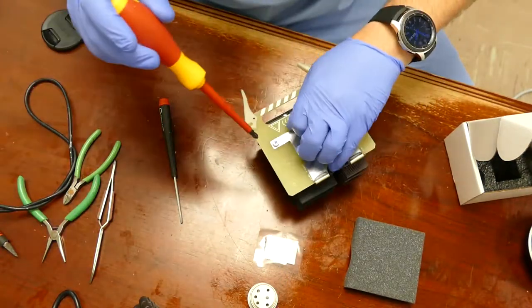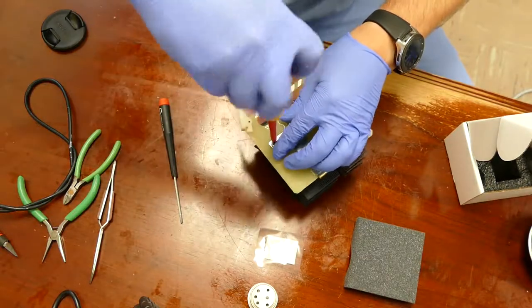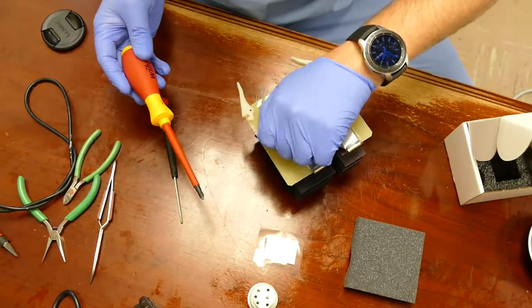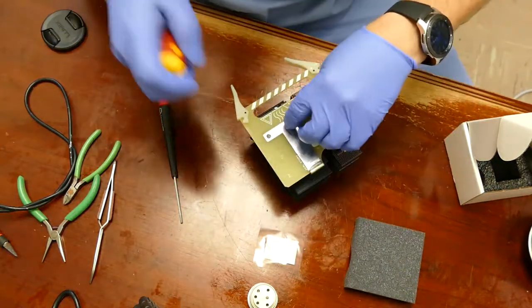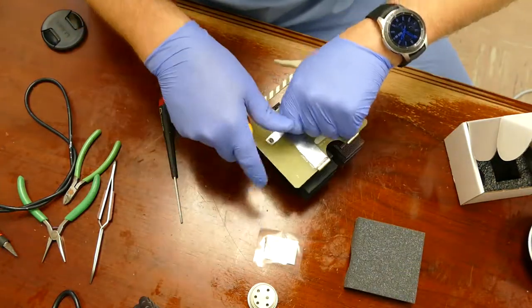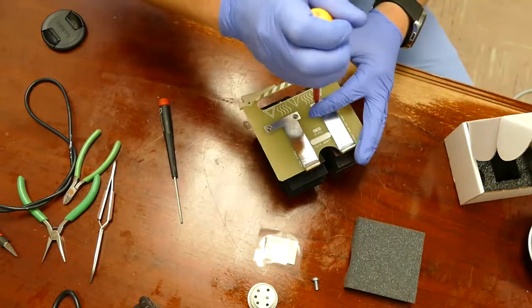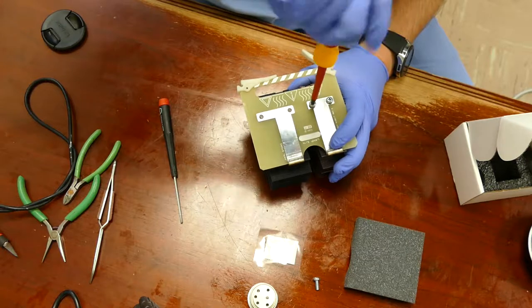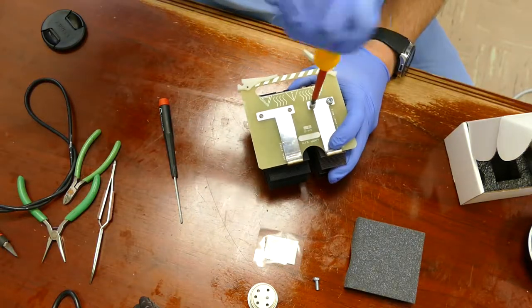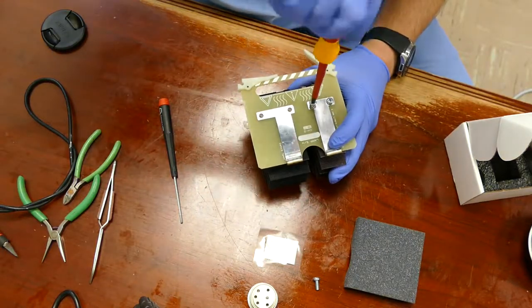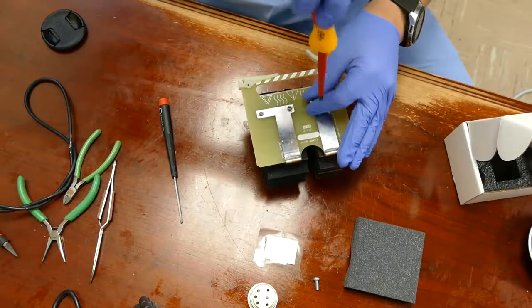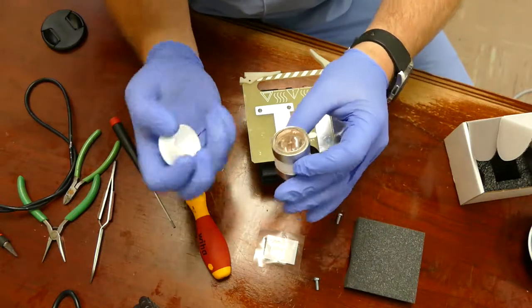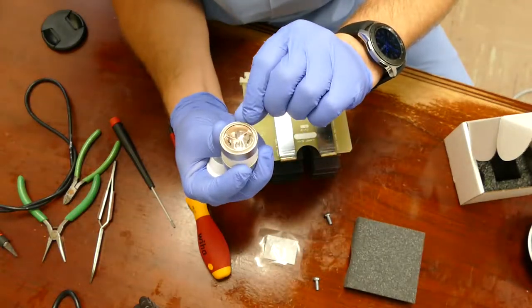I'm going to finish taking off the card. You know I'm not using power tools. The vibrations caused by power tools can also destroy the bulb. These are arc lamps, and what that means is that there is no filament. It's an electronic arc across a pressurized gas, and you can see the anode and cathode right there.